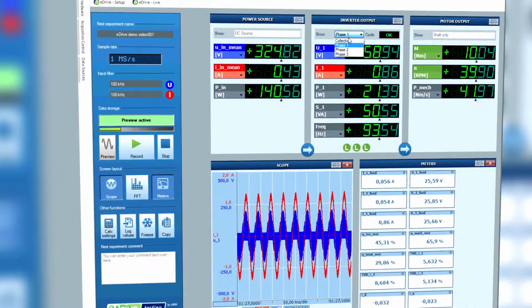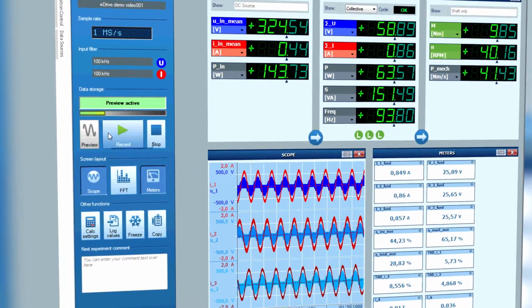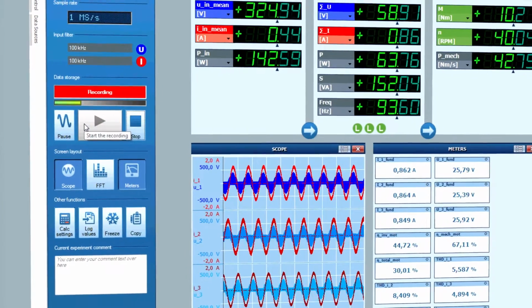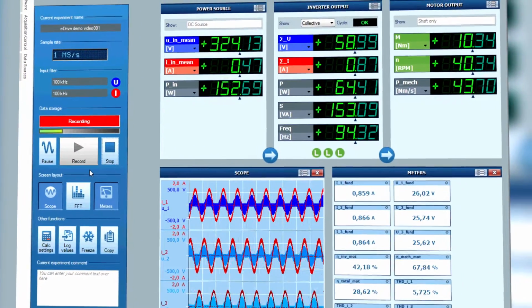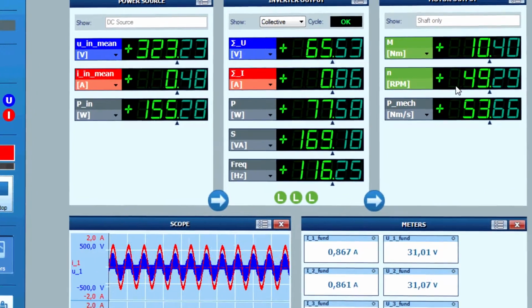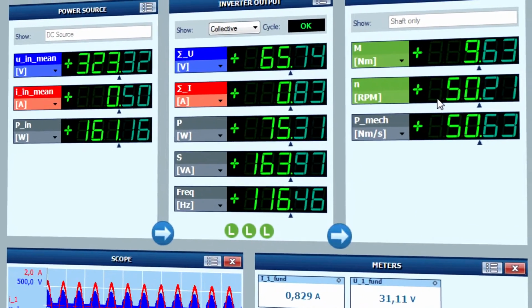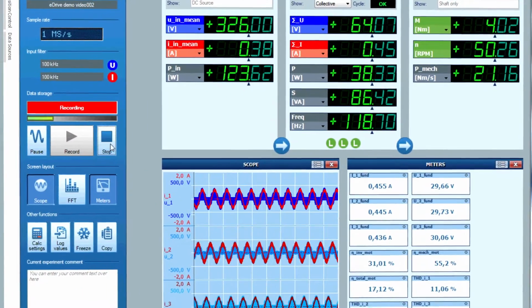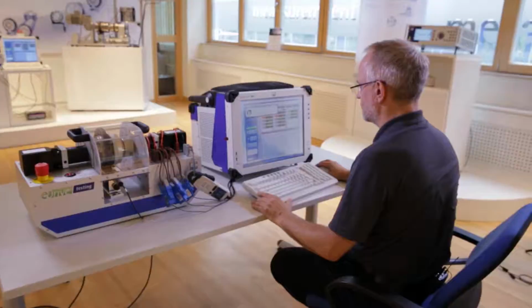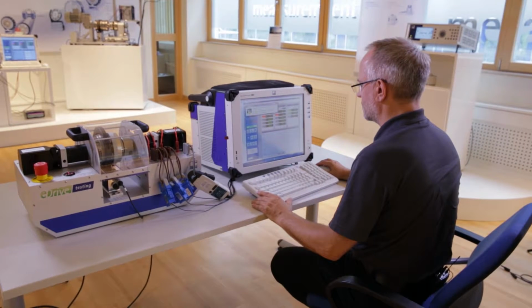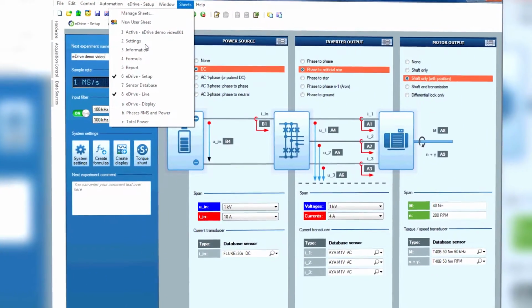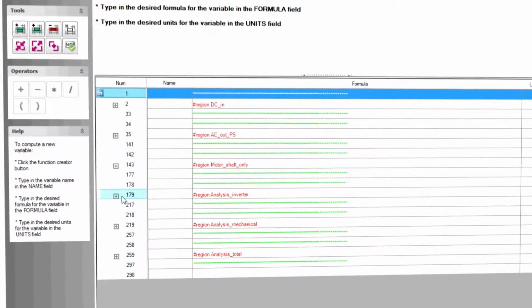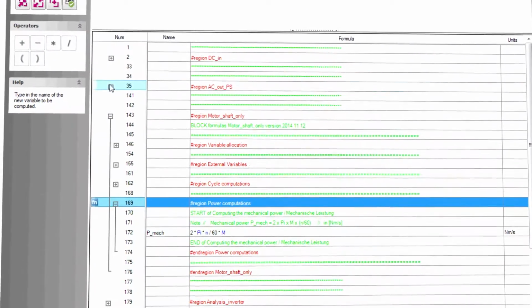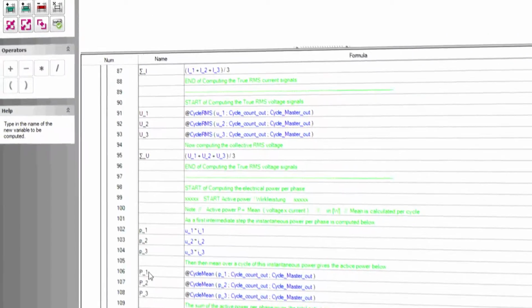Finally, we store some data so it can be used for a more detailed analysis later. Record starts the storage, and we record this initial set point for a few seconds. Then we proceed to the next set point by increasing speed and again record for a few seconds. Then we decrease torque for the last set point. Finally, press stop to end the storage. Now it's time to review and analyze the recorded data. Starting point for all post-run analysis is the formula sheet. This is pre-filled with all formulas for basic power analysis. However, each user can change existing or add custom formulas.